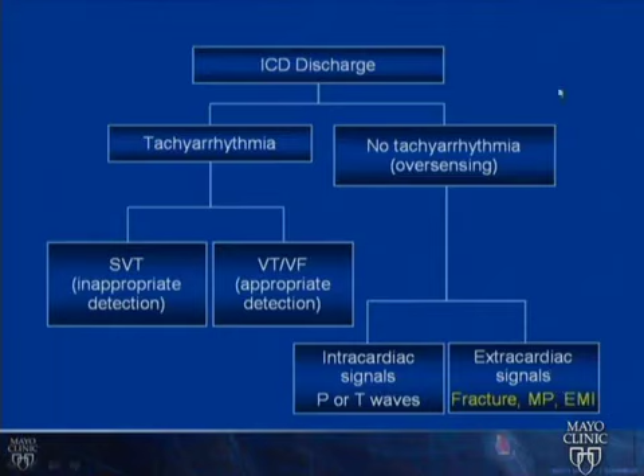That is, if the patient had a discharge but there was no tachyarrhythmia, one must consider potential interference or malfunction of the device leading to the discharge. This is a situation where a patient had a couple of shocks, and when the patient came to the clinic and the device was interrogated, with physical maneuvers, manipulating the generator and asking the patient to do a number of arm movements, one sees these noises. Here are the QRS complexes for each cardiac cycle recorded over here, but in between, you see these very discrete noises.